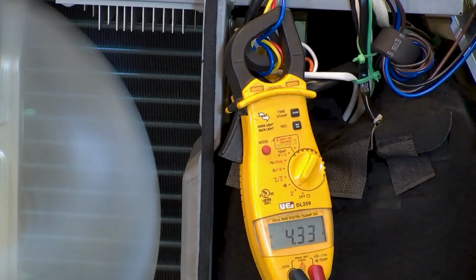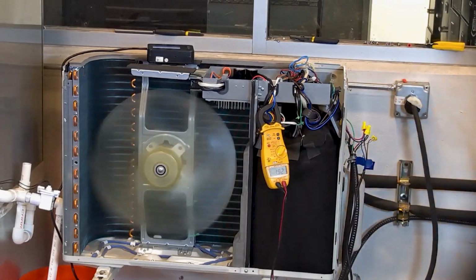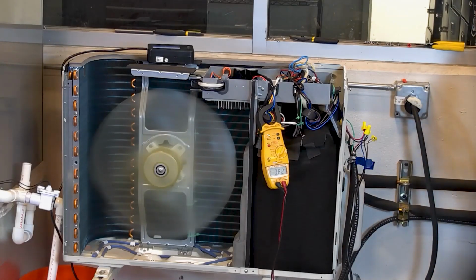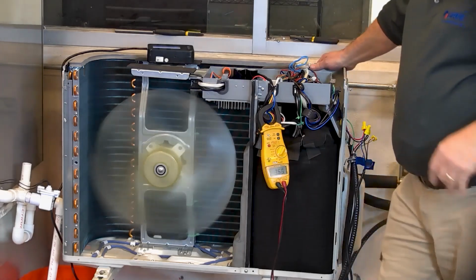Now, it could actually be a mechanically failed compressor too. If you hear that compressor in there grinding and carrying on, and I've heard them over the phone, can you listen to this thing? Okay, man, you've got a bad compressor. I'm not arguing the point. You win. But this compressor is running right now. It's pulling 4 amps. I can't even hear it. I can barely feel the vibration of that compressor putting my hand on this jacket. And this is just a little bitty, what is it, a 9K? My eyeballs are so bad anymore I can't see. But anyway, you get my point here.